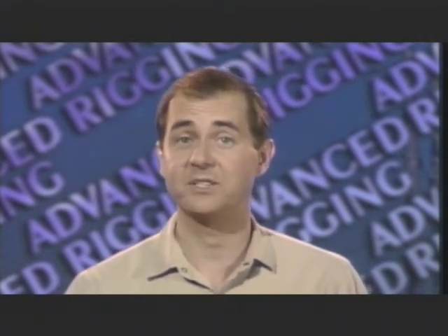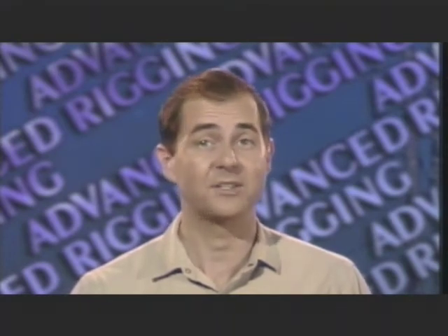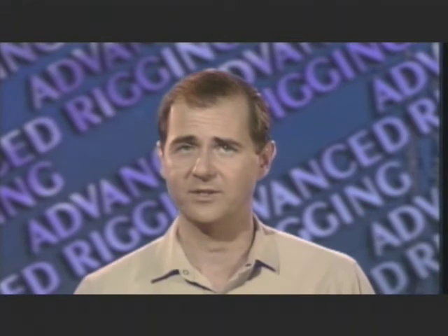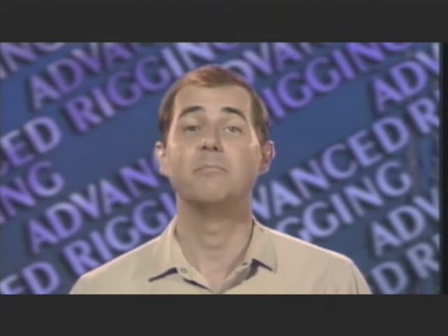Now, an important point to remember is that the same tension exists throughout the entire length of a given conductor. So, line tension can be determined from any given span so long as the span length and sag are known. Rigging to safely lift or hold the tension of conductors on tangent or dead-end poles isn't the only rigging you'll need to do. For example, you may need to move or hold a conductor that exerts a force at an angle to other poles in a line. In these cases, you'll need to determine the conductor's bisect tension.